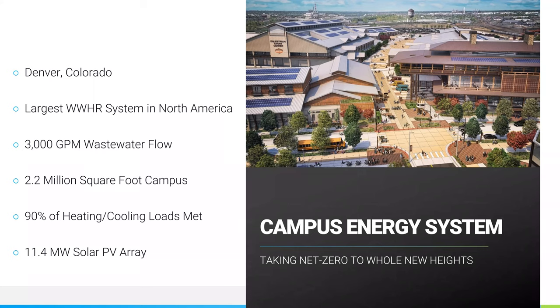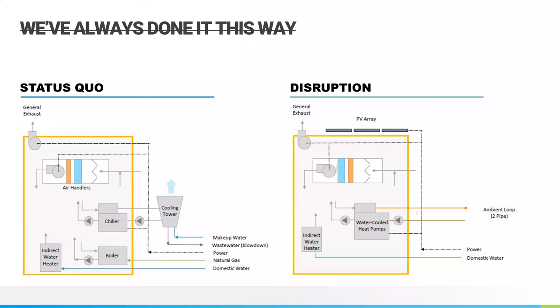So this was really taking net zero to totally new heights and showing that it doesn't have to just be building by building, and that it can actually be more cost effective when you do a campus or district style. Looking at your typical campuses, traditionally how they've done it is a building by building approach, where they'd have a heating and cooling system for each building, and may have a cooling tower if it's water cooled. You've got a separate system creating air conditioning, a separate system creating hot water, and a separate system creating heating. So it's very clunky, with lots of moving parts. And truly, in my opinion, it's a Cro-Magnon way of looking at district energy systems.